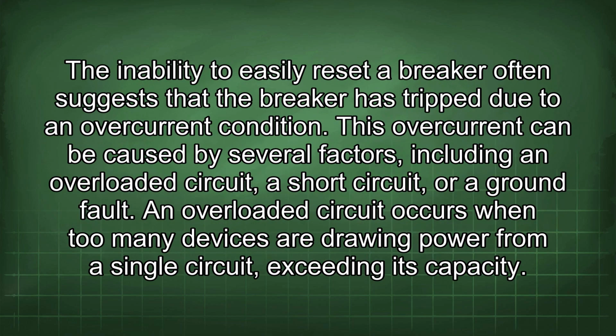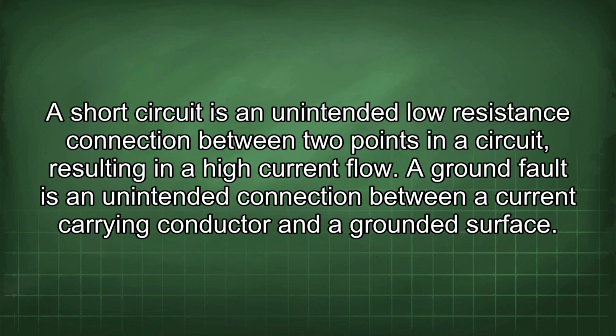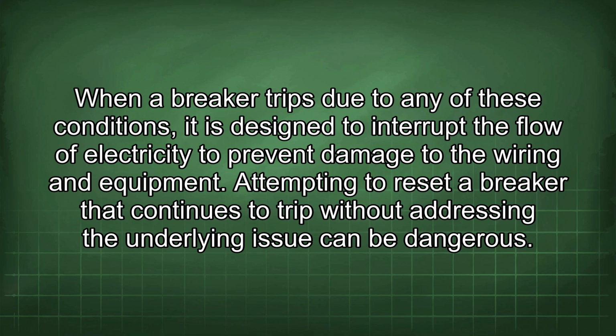The inability to easily reset a breaker often suggests that the breaker has tripped due to an overcurrent condition. This overcurrent can be caused by several factors, including an overloaded circuit, a short circuit, or a ground fault. An overloaded circuit occurs when too many devices are drawing power from a single circuit, exceeding its capacity. A short circuit is an unintended low-resistance connection between 2 points in a circuit, resulting in a high current flow. A ground fault is an unintended connection between a current-carrying conductor and a grounded surface. When a breaker trips due to any of these conditions, it is designed to interrupt the flow of electricity to prevent damage to the wiring and equipment.